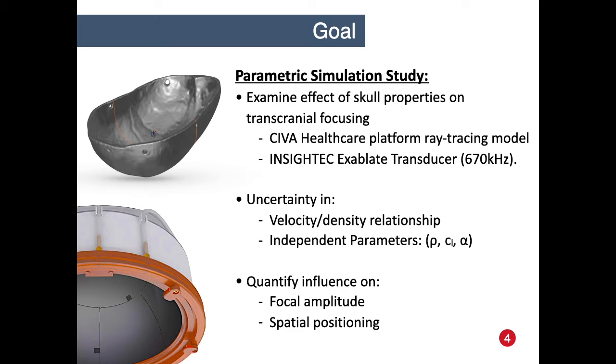properties on transcranial focusing. Our parametric study used a ray tracing model provided by the CIVA Healthcare platform and a transducer based on the Insightec Exablate transducer operating at 670 kHz. First, we quantify the effect of variation between the different conversion algorithms to obtain skull velocity, and then we look at how variation of independent parameters affected the focalization quality. To quantify the focalization error, we looked at the maximum acoustic amplitude obtained from simulations and the change in the position at which the maximum amplitude occurs.